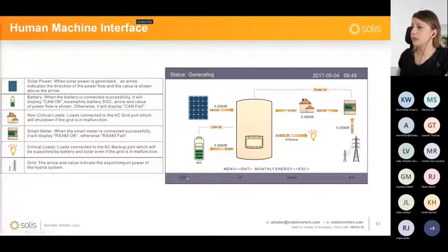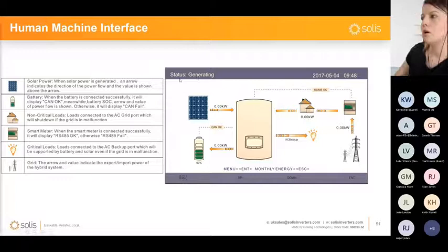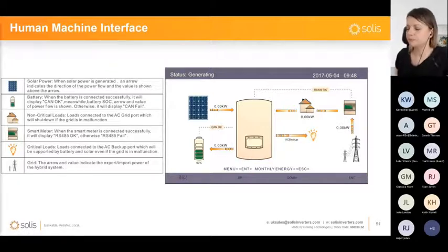Okay, and what I haven't mentioned, there's an escape, up, down, and enter button here. Always on the top, you're going to see a status for generating. This is a scrolling status, and it's going to also show which storage mode is selected, if it's self-use or backup. Additionally, if there are any alarms active on the inverter, you're going to see the alarm LED is on, but also here you're going to see the active alarm code. So it can be no battery or no grid, or most of them are quite explicit. Others, you can find some description for the most common ones in the user manual as well.